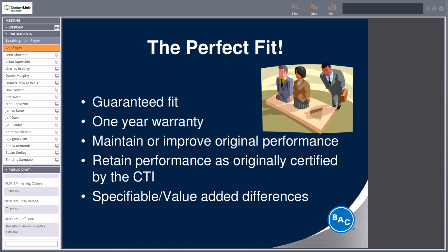Again, this is kind of a crossover for the parts and design. We can upgrade your tower depending on how old it is. We can switch to a premium efficient fan motor. We can improve the fan design. We do have several projects that get retrofitted where they want to add a little bit more capacity that can't be maintained with the existing tower. We might be able to put on a bigger fan motor. We might be able to put on a different fan to give you a little bit more performance. And again, that's all stuff that we can help with the design on.